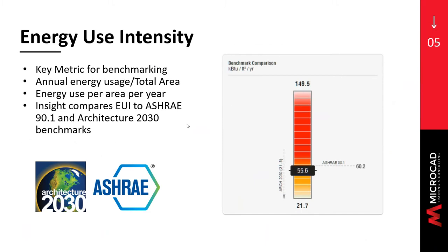The main feature you're going to see with Insight is a key metric called the EUI, or Energy Use Intensity. Factors such as lighting, HVAC system types, and plug loads all affect your EUI, which is the key metric for benchmarking your buildings. The EUI is calculated as the annual energy use divided by the total area of your building. Insight compares the EUI to either ASHRAE 90.1 or the Architecture 2030 benchmark, allowing you to get closer to the performance levels required for your project.